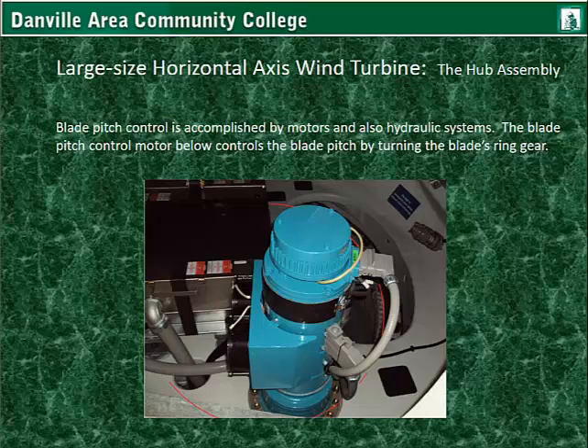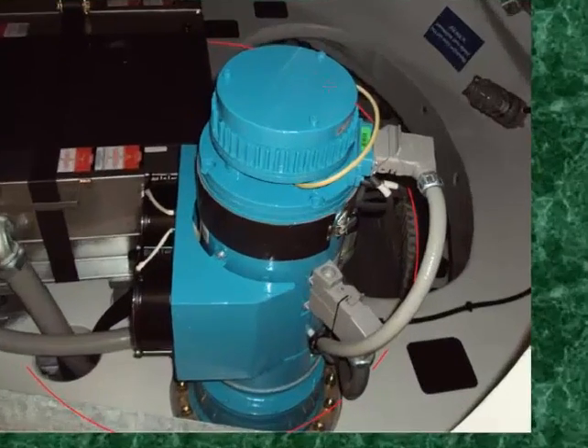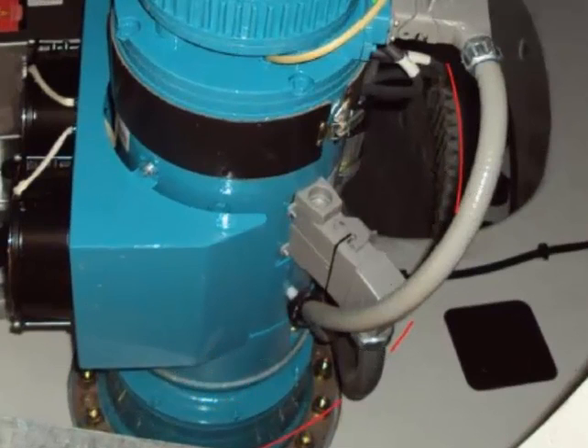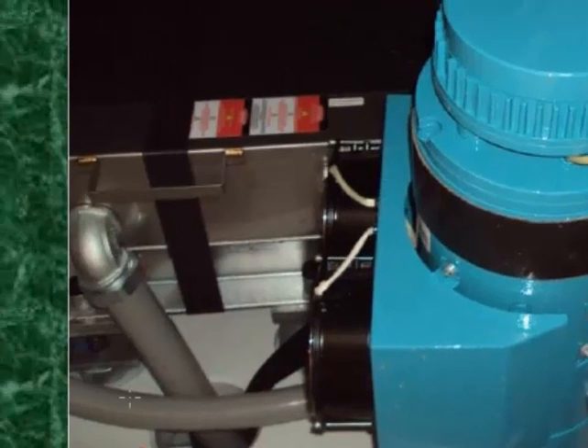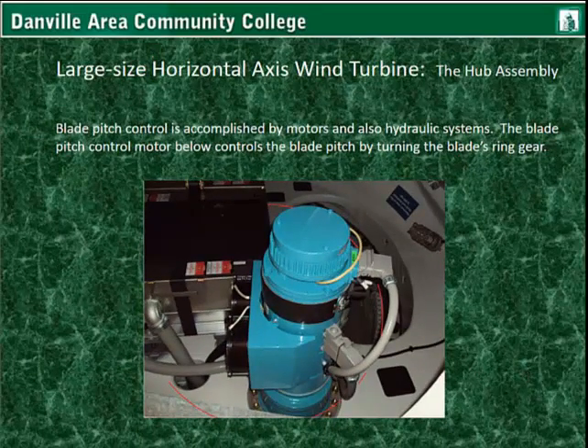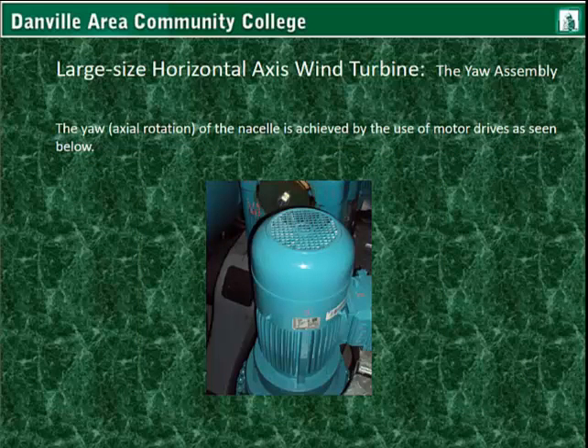The blade pitch control is accomplished by motors and also hydraulic systems. The blade pitch control motor controls blade pitch by turning the blade's ring gear — the drive end has a gear, and the root of the blade on the inside has a gear. Control systems and cooling fans for the motor are also present. The yaw — the vertical axis rotation of the nacelle — is achieved by motor drives that mount through the bed plate to the yaw gear, rotating in sync to slowly turn the nacelle into or out of the wind.